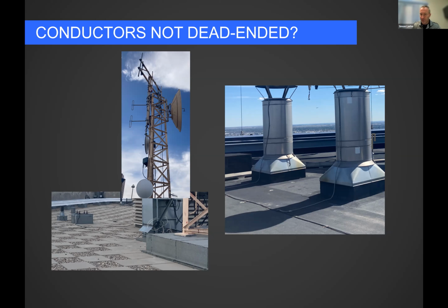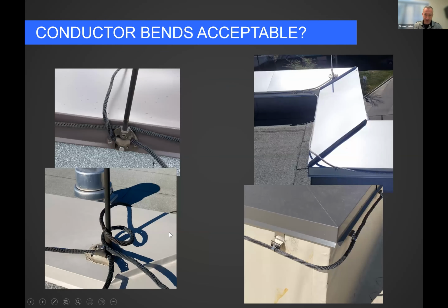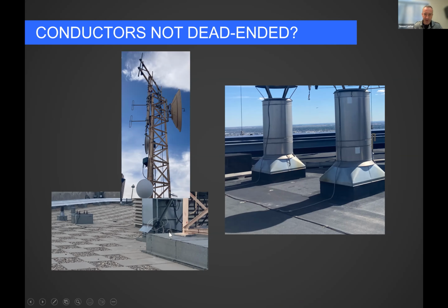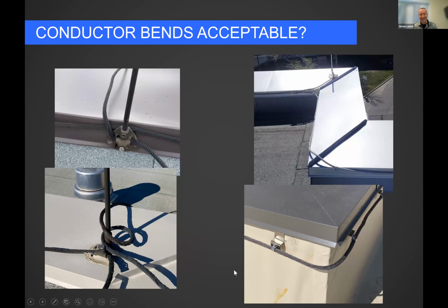We don't worry about the vertical component of it, but that horizontal run there over to the main lightning conductor can't be more than 2.4 meters or 8 feet, whatever it is. So we want to keep those dead ends short. Meanwhile, that antenna there, that's dead ended with a single path to ground that goes probably 6 meters back to the main conductor. So that one was a non-compliant dead end.